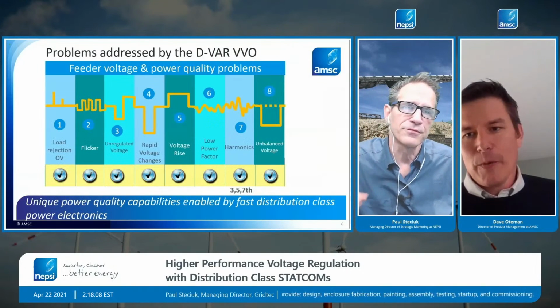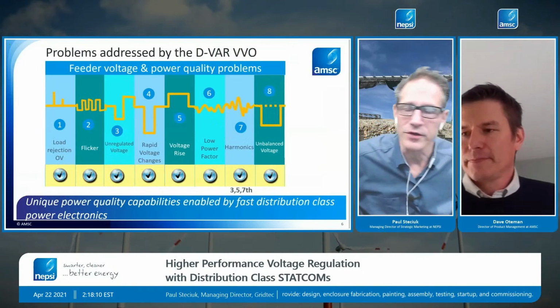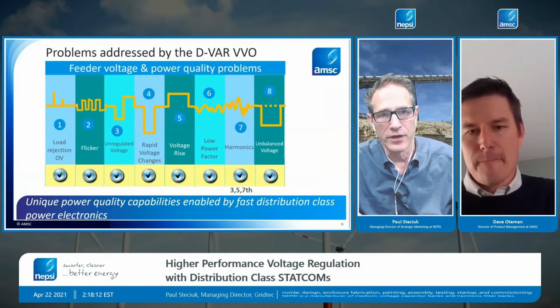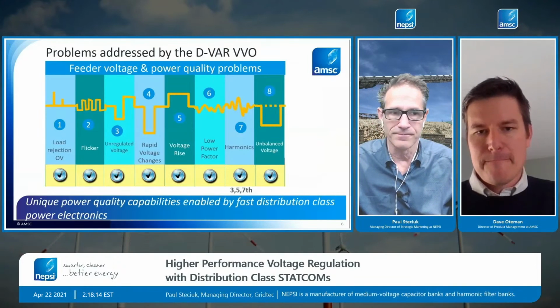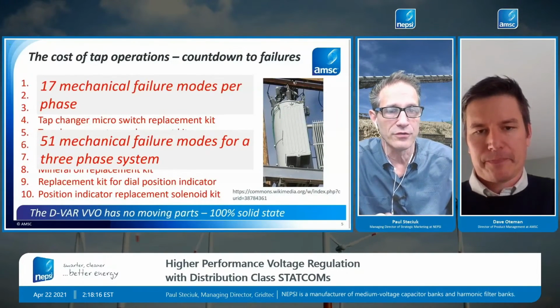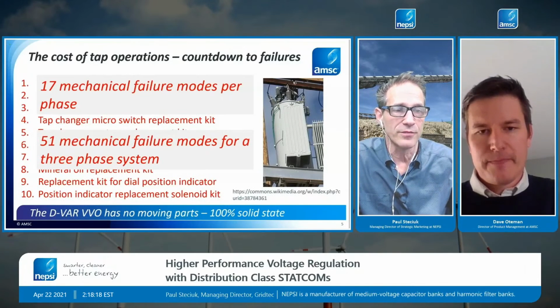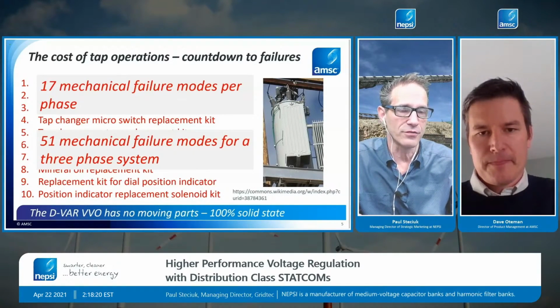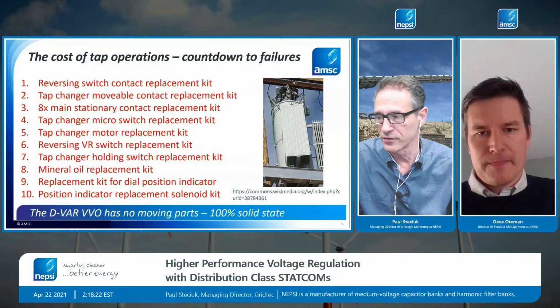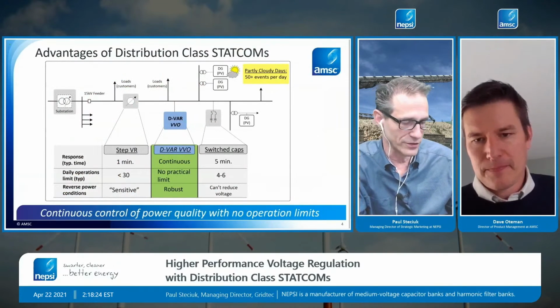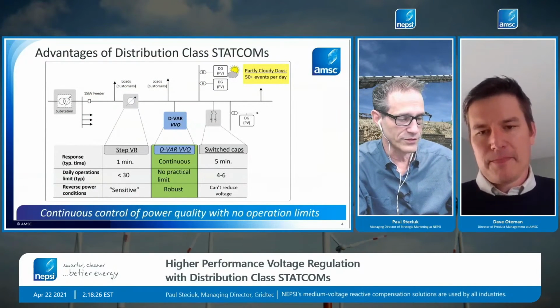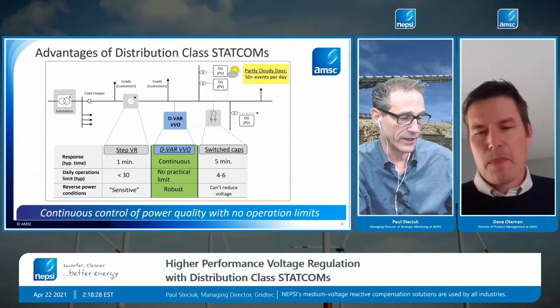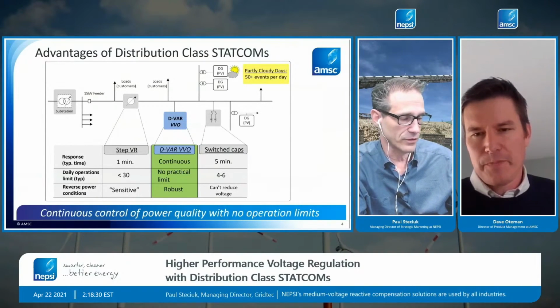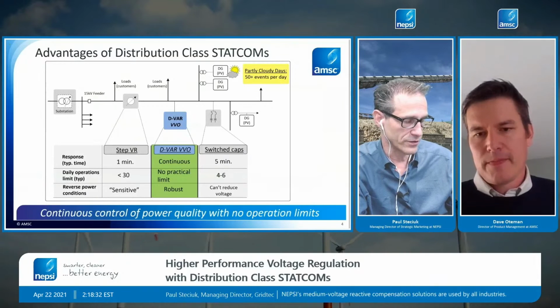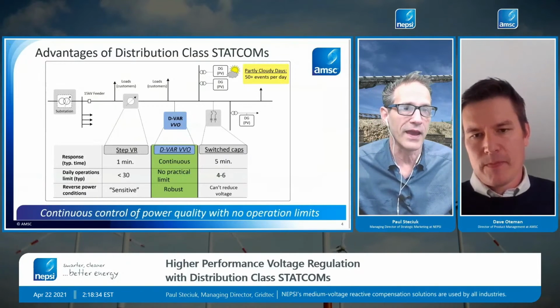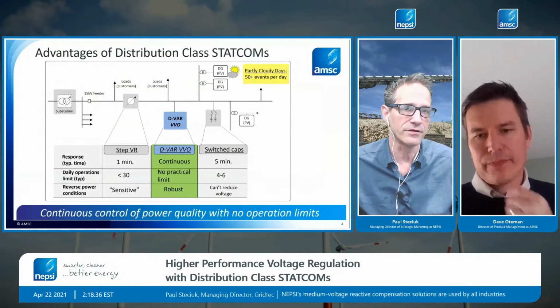So Dave, let me just summarize. Cap banks are mechanically switched, and we've talked about mechanical switching before. For capacitor banks, typically 10,000 operations is what a vacuum switch is rated for. So if you do a simple calculation, if you're doing four switching operations a day, that's 2,500 days' worth of operations. So maybe 6 years max that you might get out of that switching device.